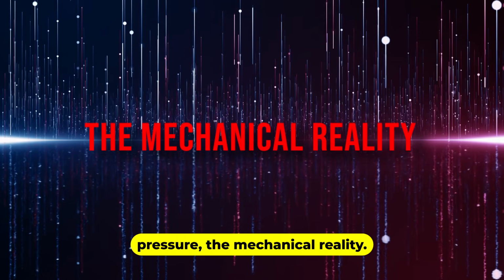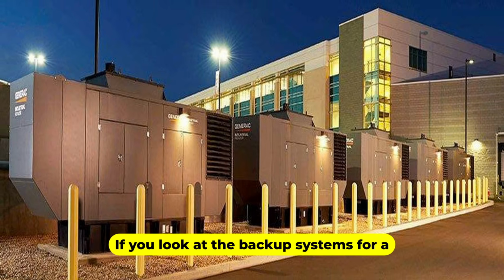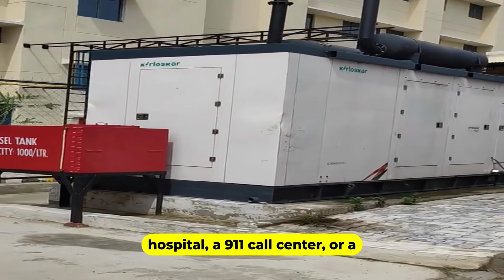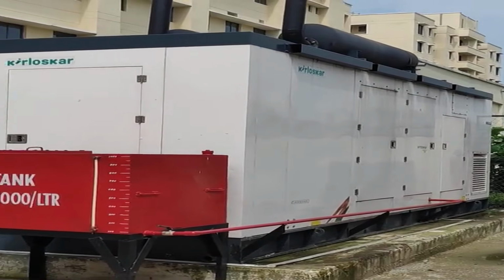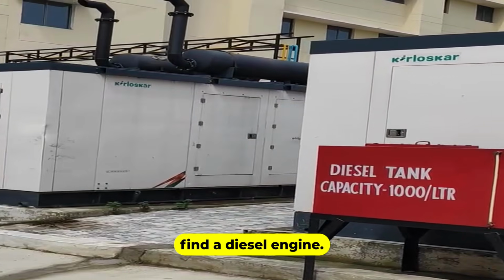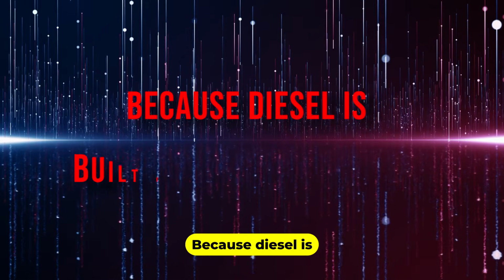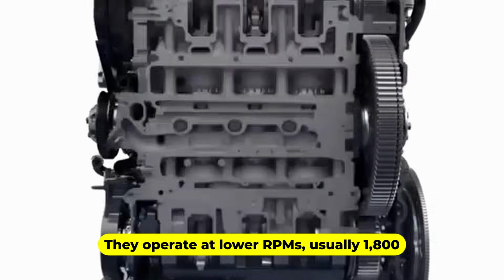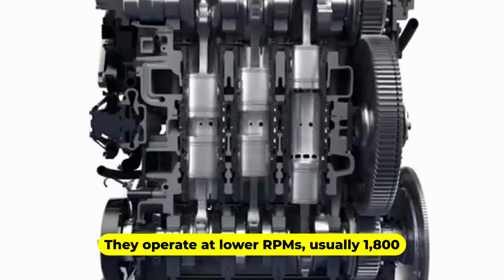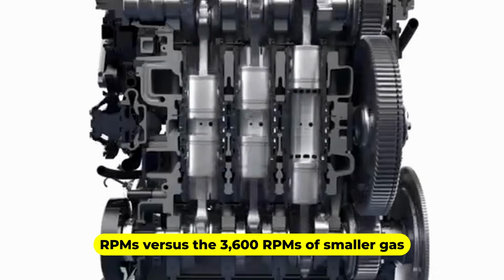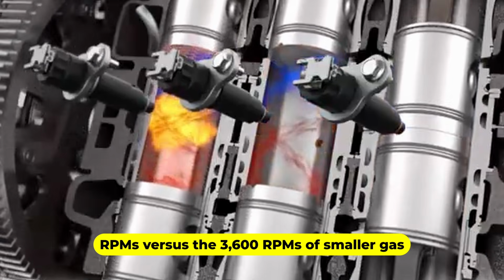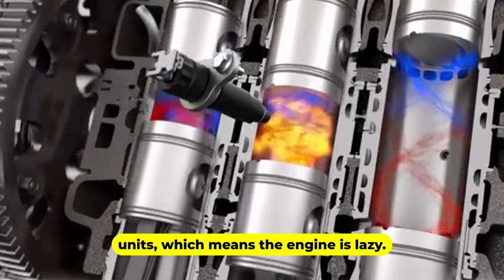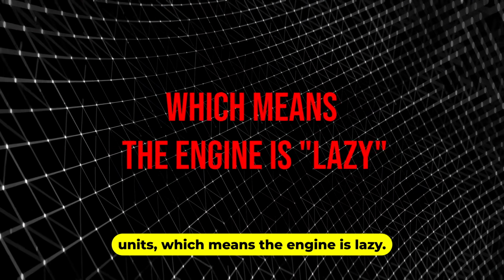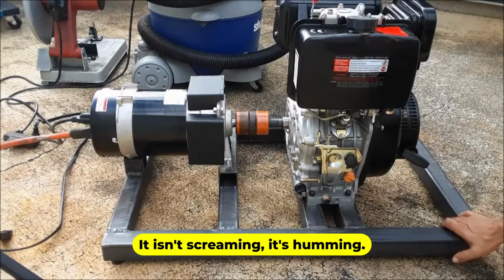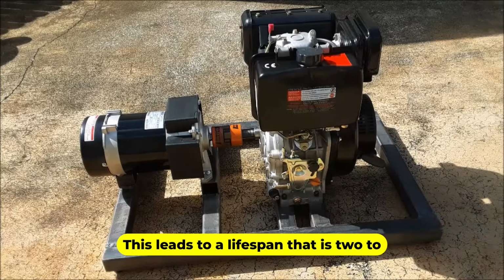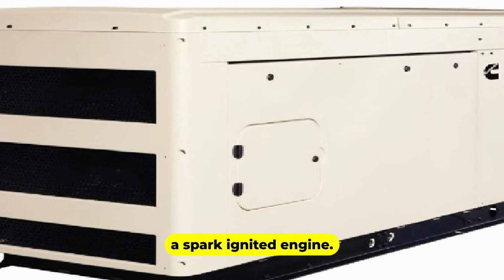The mechanical reality. If you look at the backup systems for a hospital, a 911 call center, or a billionaire's estate, you will almost always find a diesel engine. Why? Because diesel is built for the long haul. They operate at lower RPMs, usually 1,800 RPMs versus the 3,600 RPMs of smaller gas units, which means the engine is lazy. It isn't screaming, it's humming. This leads to a lifespan that is 2 to 3 times longer than a spark-ignited engine.